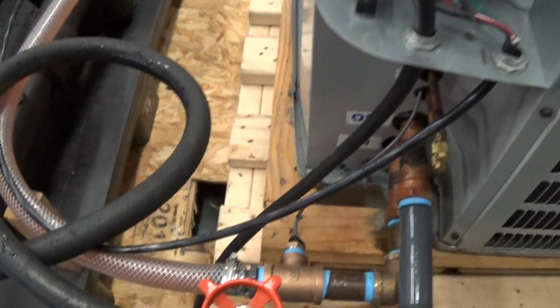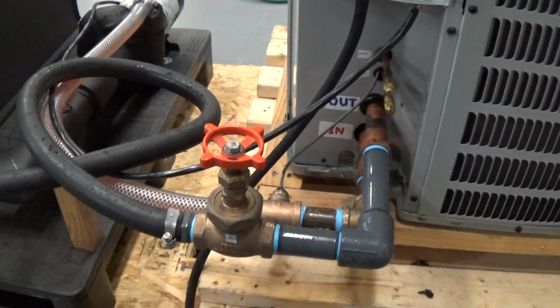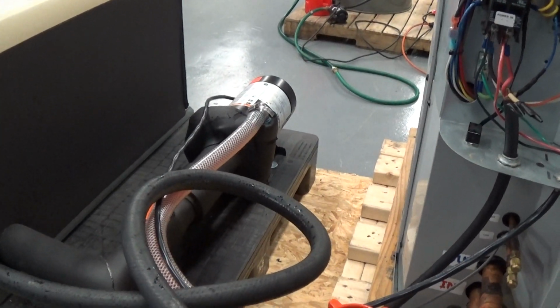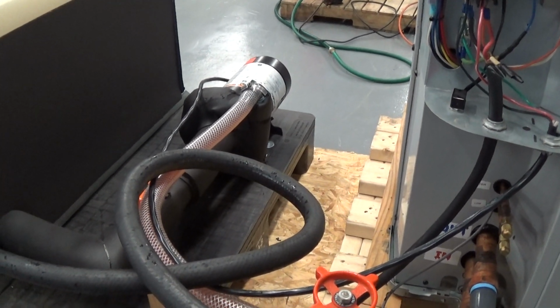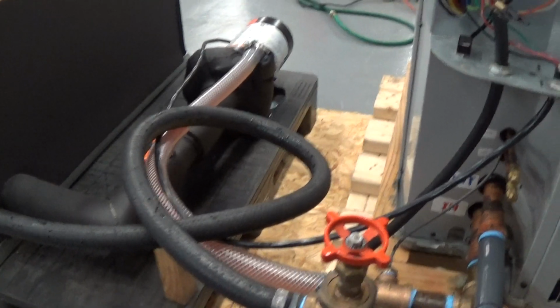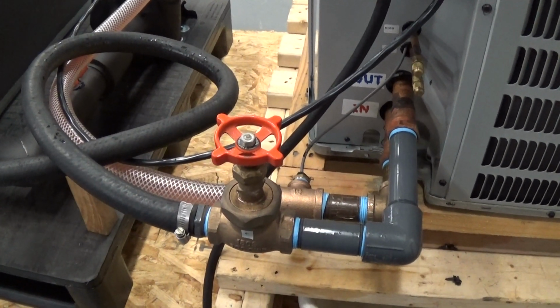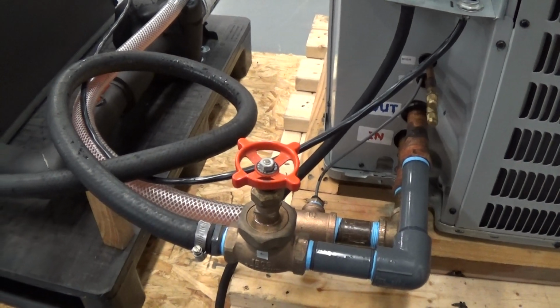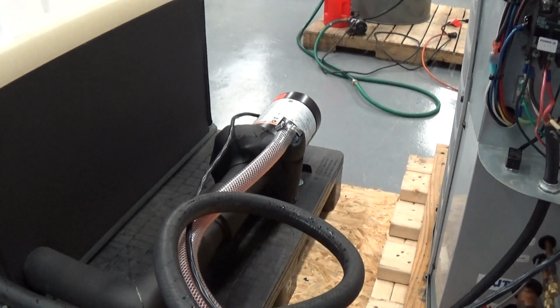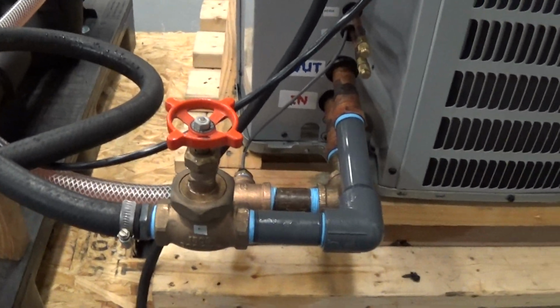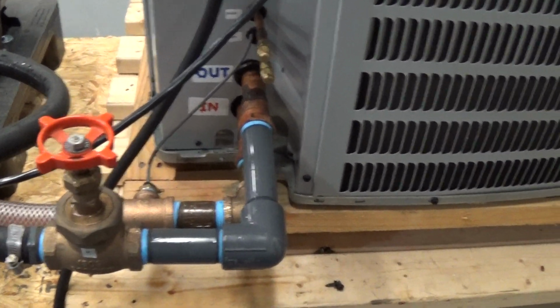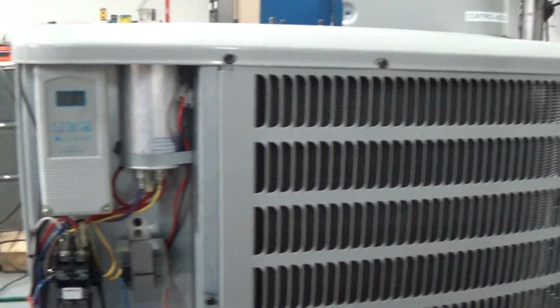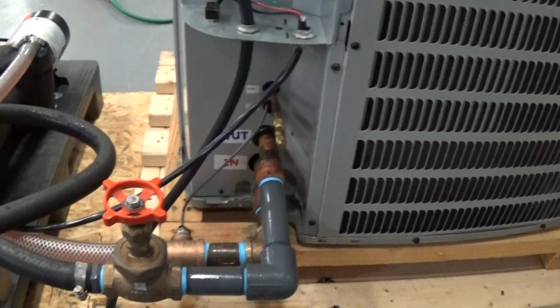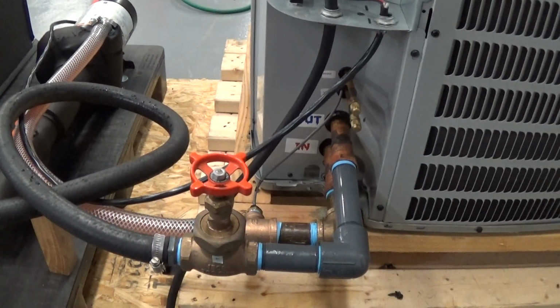Very important that you have an amp meter while you're dialing in the system to make sure that when all your tanks are calling for cooling, which is the worst scenario, it's going to be pumping the most, that the pump is not over amping. That's the biggest startup issue. Pump likes to see some back pressure. So it's common that you dial back on valves or shutoffs going into each one of your tanks, that you throttle those down so that we're not overamping the pump. We have a startup guide that we can email you, although for a different configuration chiller, it applies on how to dial the system in, particularly for dialing in the pump amps.